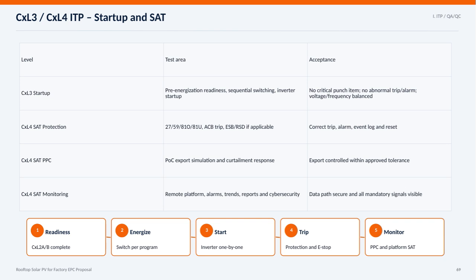For CXL4 SAT PPC, we simulate power export and curtailment, making sure export levels stay within the approved tolerance. Finally, in CXL4 SAT monitoring, we validate the remote platform's security and visibility by checking alarms, trends, reports, and cybersecurity measures. The step-by-step sequence moves from readiness, with CXL2A complete, to energizing equipment, switching per program, starting inverters one by one, testing the trip functions including protection and emergency stop, and finally monitoring PPC performance and platform functionality through SAT. Each step is critical to ensure a smooth and safe system startup and acceptance testing.